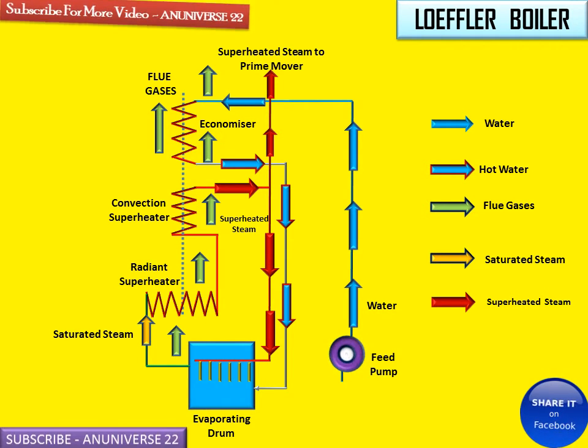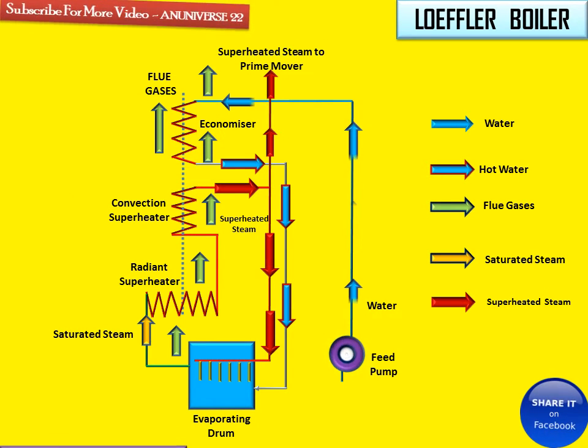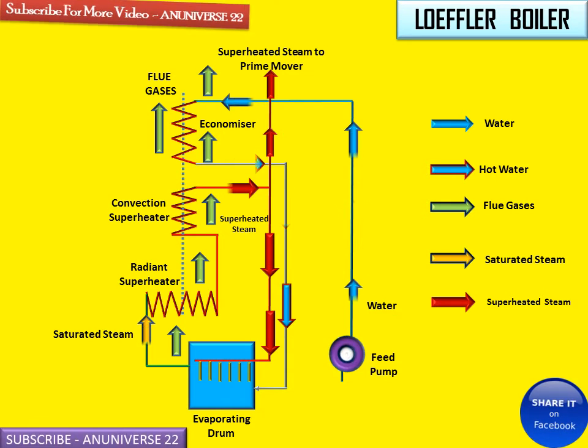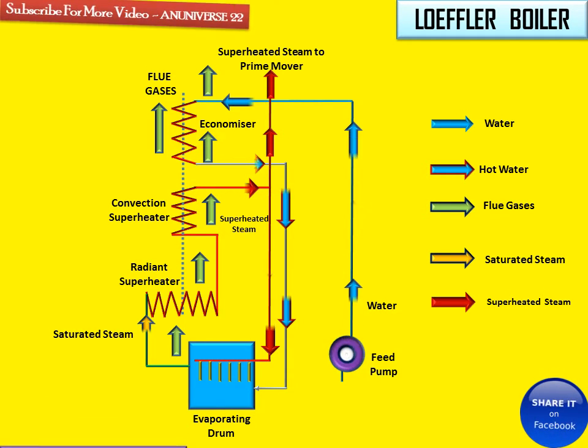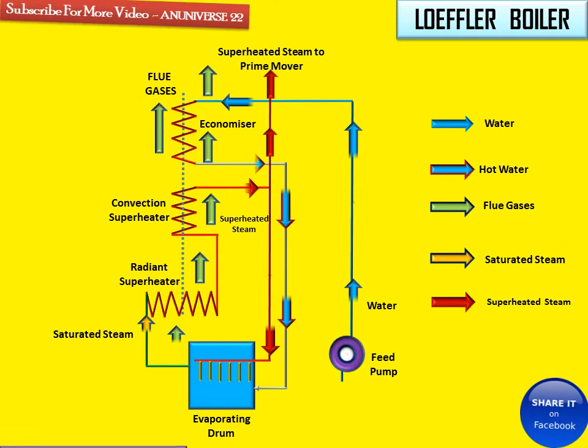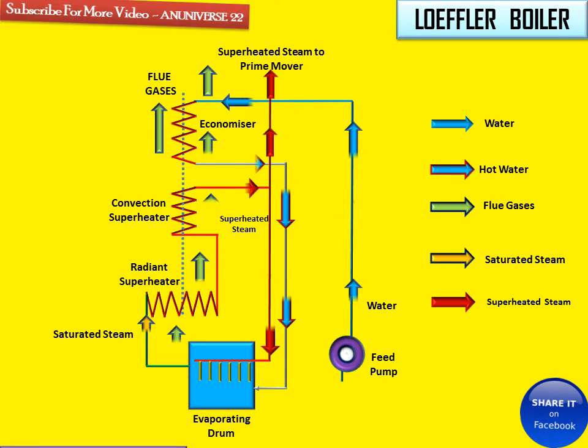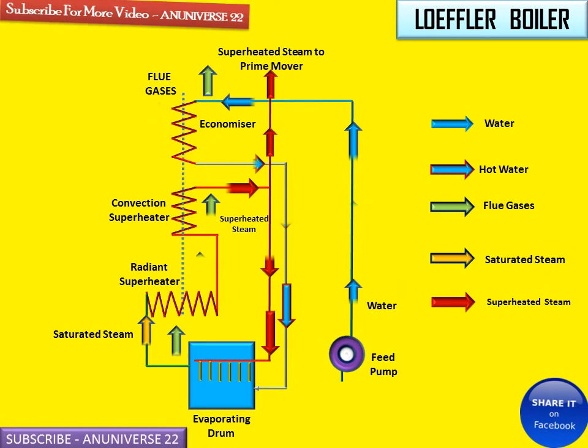As the feed pump starts to rotate, there is a continuous supply of water to the economizer, and water is supplied to the evaporating drum. From the evaporating drum, saturated steam goes to the radiant superheater, then from the radiant to the convection superheater. From the convection superheater, steam is supplied to the evaporating drum, and the remaining portion goes to the prime mover.